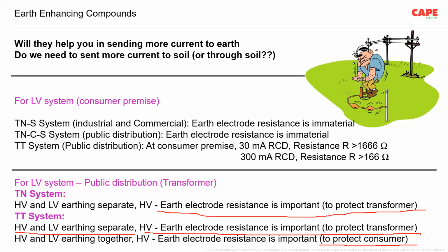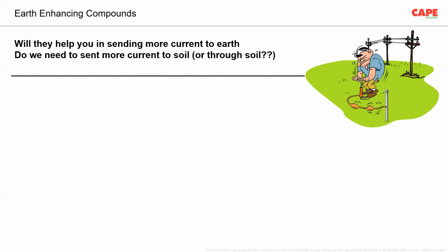Number two, if they go for TT system, if they want to make HV and LV separate, in order to protect the transformer, earth electrode resistance is important. Now, if HV and LV is together, in order to protect the consumer premise, earth electrode resistance is important. But if we look from the point of regulation, actually we are supposed to follow TN system and not separate, connected together, so that everything is safe.